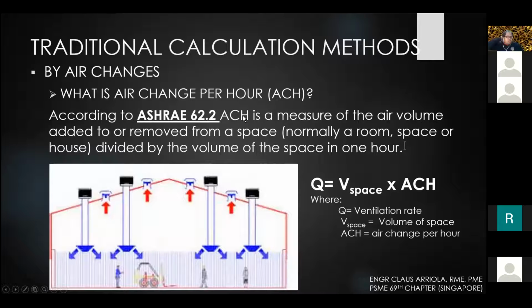Okay, traditional calculation methods. How do we design? One of the methods to calculate the volume of air we need to extract, or input to the space to pressurize it, is by air change. Air change is equal to the measure of air volume added or removed from a space divided by the volume of the space in 1 hour. So that is air change.